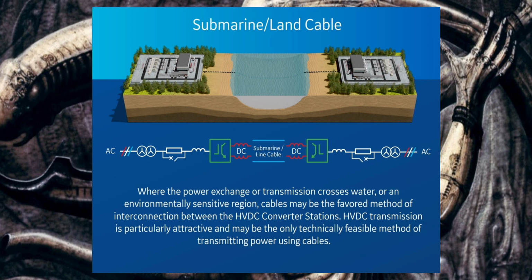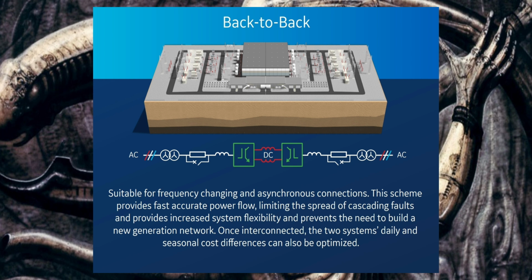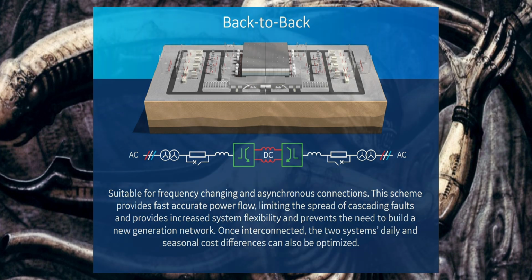HVDC submarine or land cables for power transmission may be used across water bodies or environmentally sensitive regions. This method is preferred due to its technical feasibility and efficiency in reducing power losses over long distances, making it ideal for interconnecting HVDC converters. Back-to-back HVDC systems enable the interconnection of two asynchronous AC grids. These systems allow for frequency conversion, improve power flow control, and enhance grid stability by preventing cascading faults. They provide flexibility in power exchange without requiring new generation.